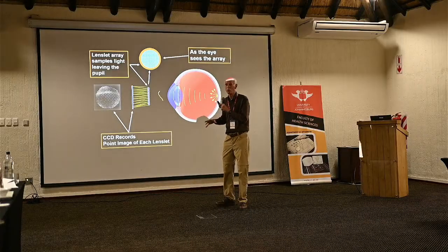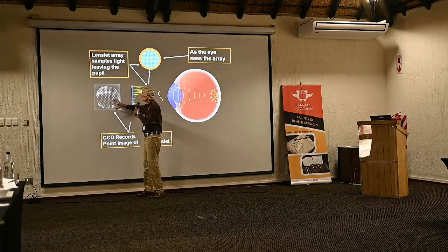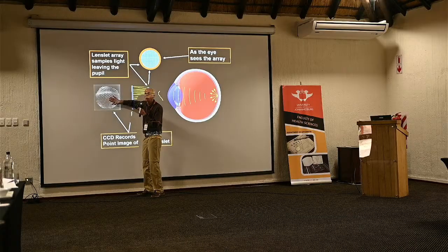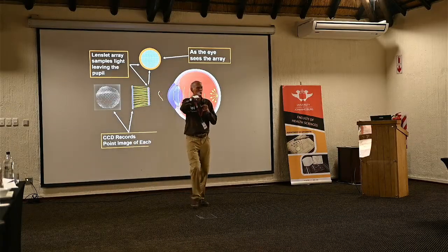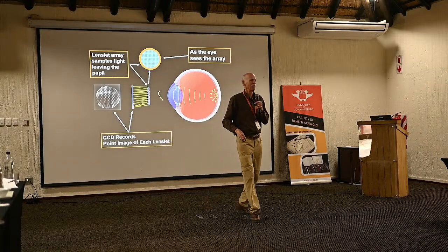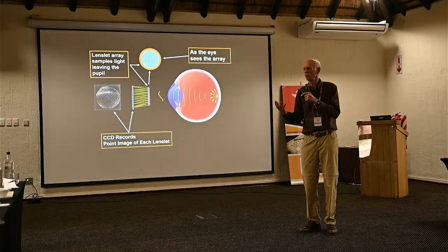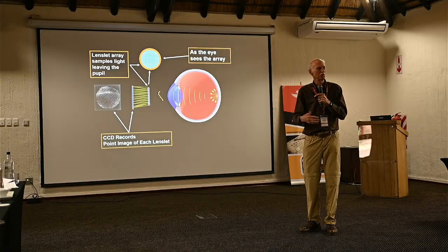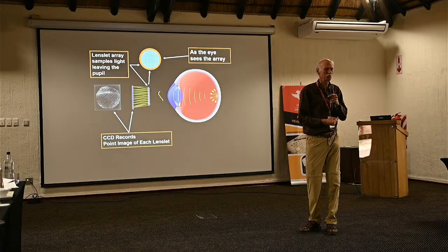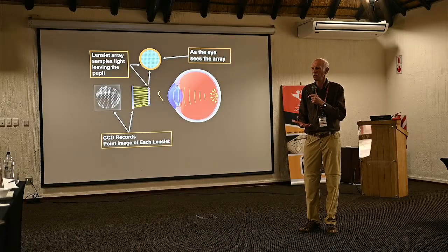And see, many of these aberrometers estimate the pupil's diameter and location based on this image. But that's kind of illogical because all those little spots have moved. Those spots have been moving around because of aberrations. You're going to get an aberrated sense of how big the pupil is and where it's centered. It seems like it's all wrong. I think that's a bad design. And some of the early aberrometers made that kind of error.